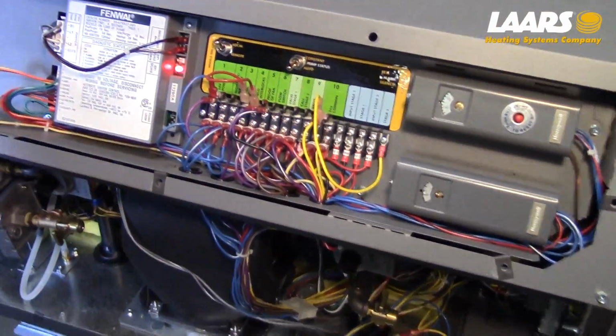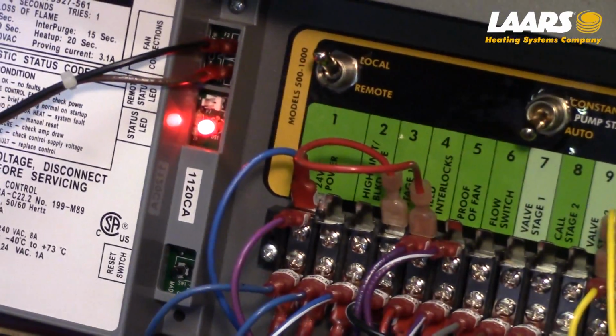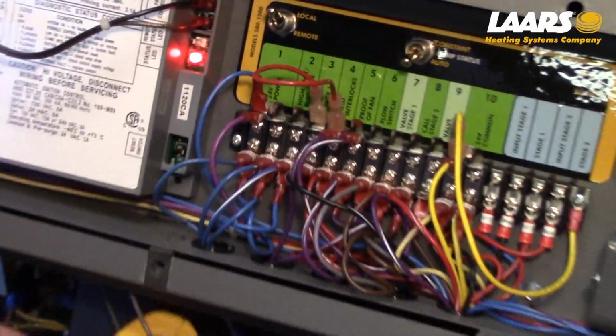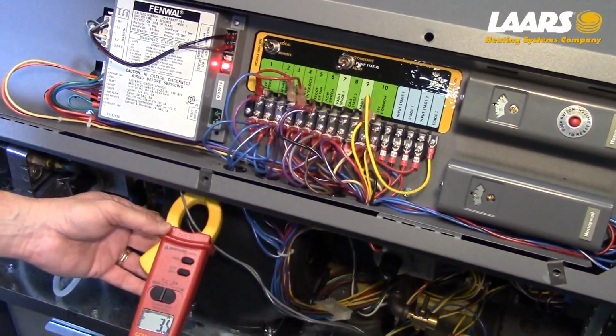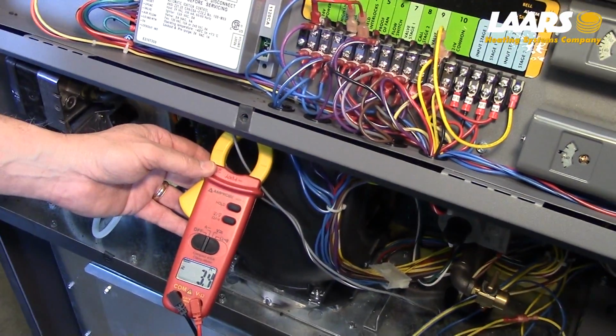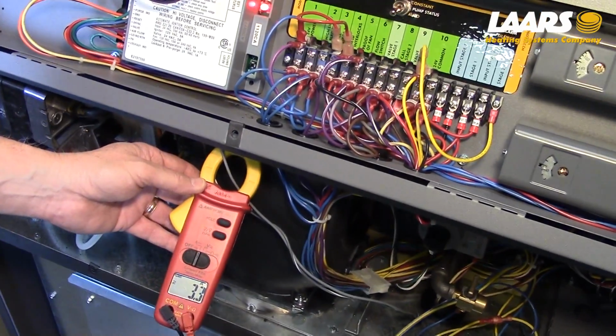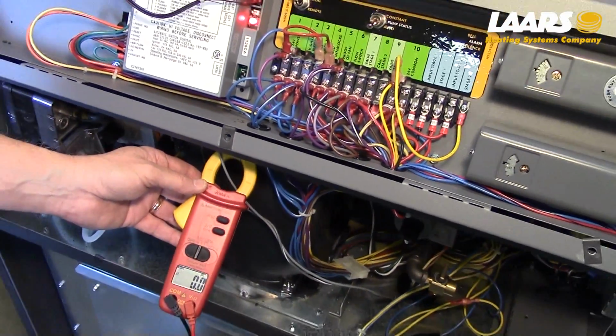Looking at our ignition control, you'll see that single flash. That's telling me my igniter is now being energized. I'm going to put an amp probe on there, and we're looking for 3.4 amps or greater. And now we just lit off.